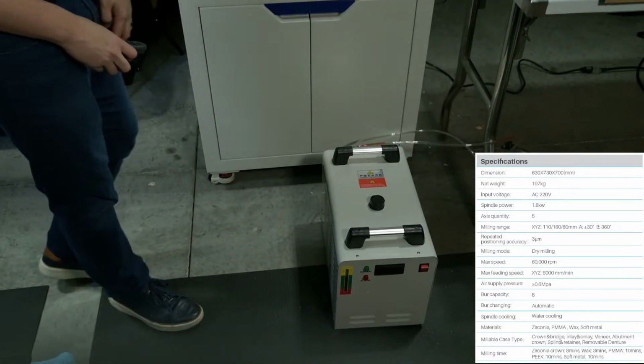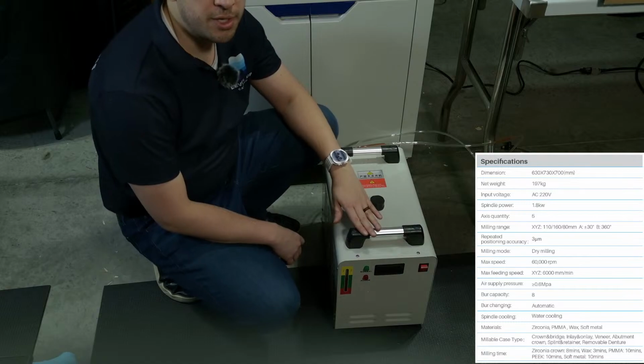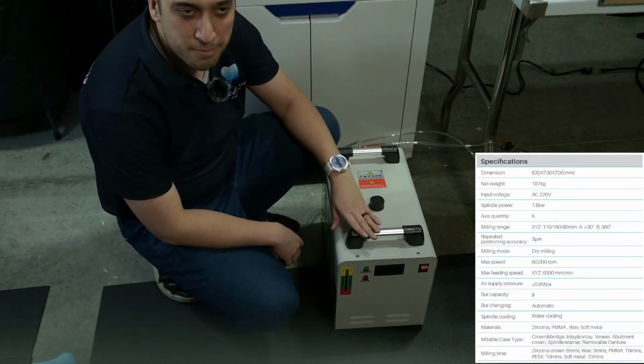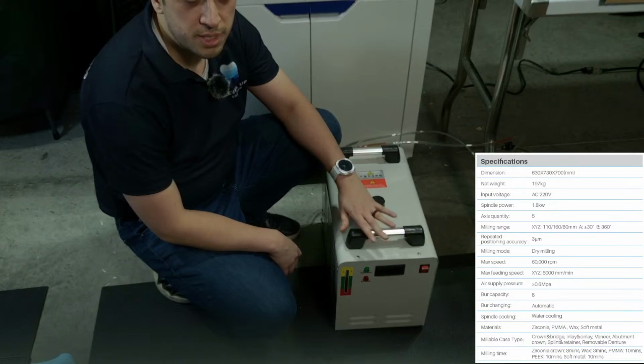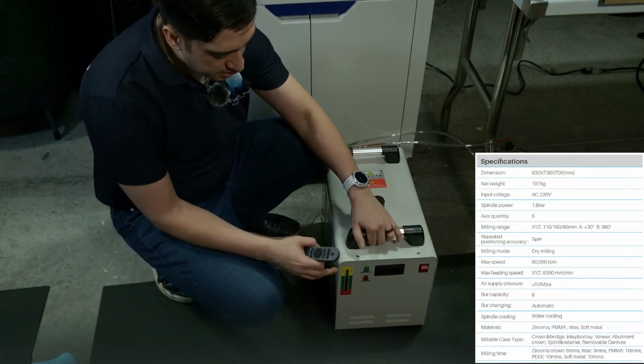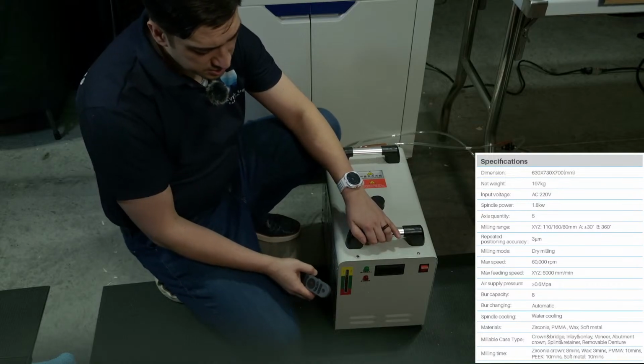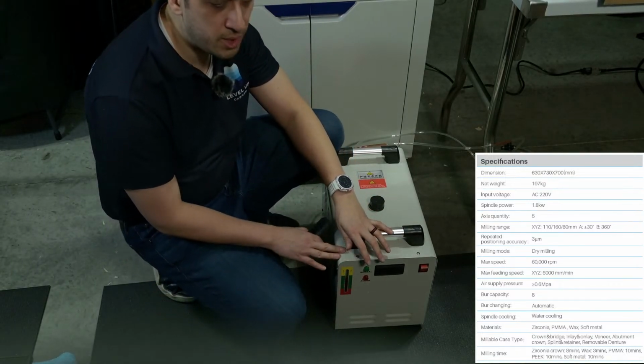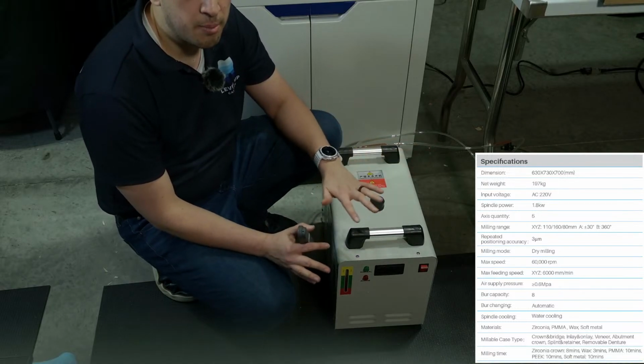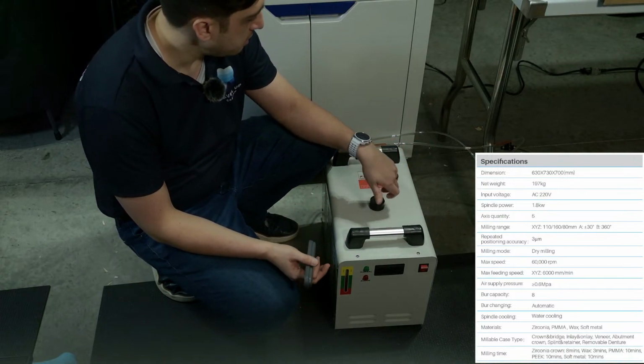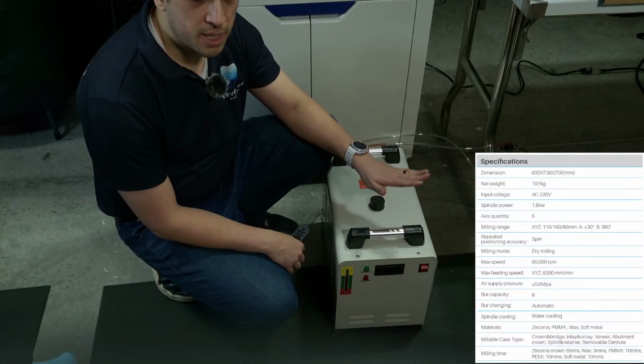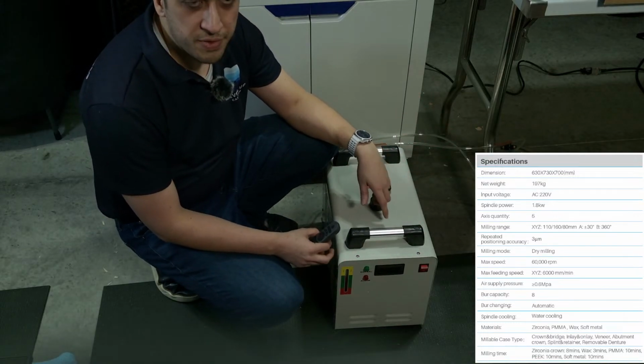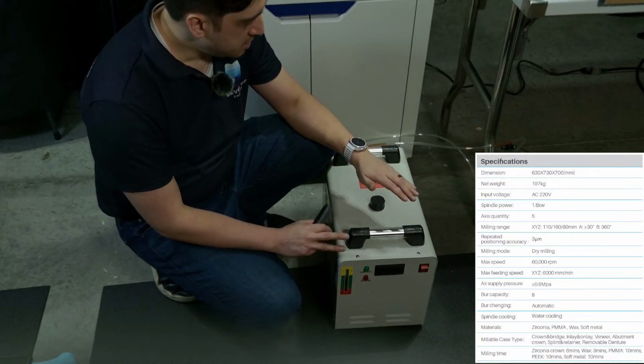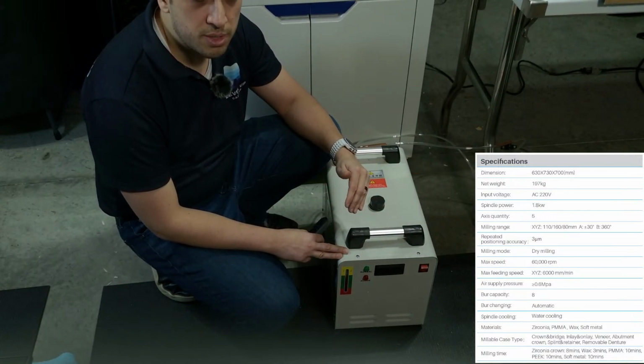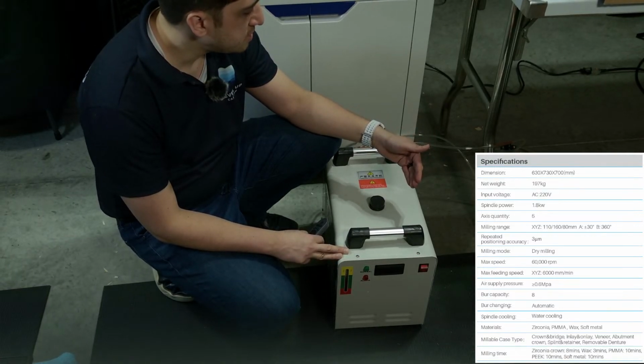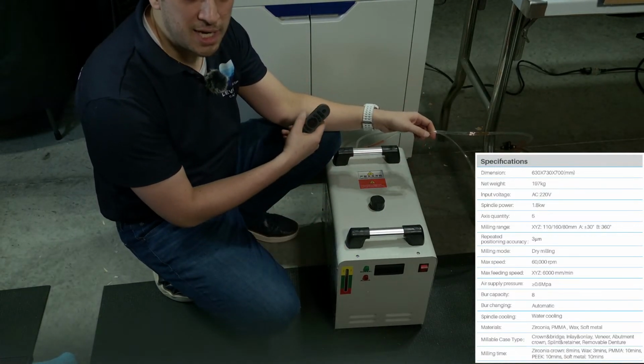All right, so this right here is our industrial chiller. We have some recommended coolant that you can purchase local to the US domestic market to fill it up. Basically there's a fill meter, you just want to keep it topped off. The coolant in this machine is really the number one preventative maintenance that you have to worry about on a yearly basis. Once a year, if you go a little bit longer I don't think it's going to cause a big deal, but typically at the year cycle is when you want to drain out all the coolant from the system.